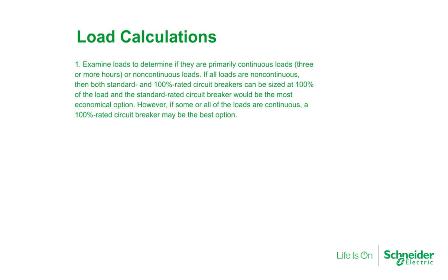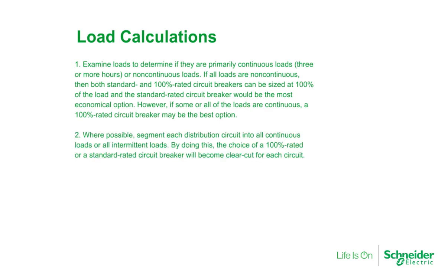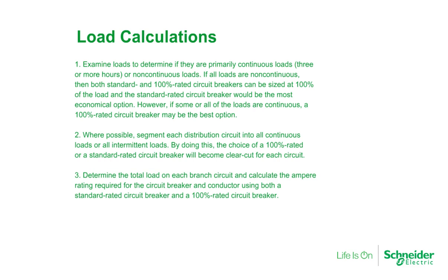However, if some or all of the loads are continuous, a 100% rated circuit breaker may be the best option. Where possible, segment each distribution circuit into all continuous loads or all intermittent loads. By doing this, the choice of a 100% rated circuit breaker or a standard rated circuit breaker will become clear-cut for each circuit. Determine the total load on each branch circuit and calculate the ampere rating required for the circuit breaker and conductor using both a standard rated breaker and a 100% rated circuit breaker.